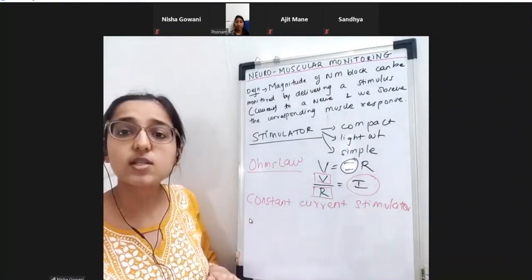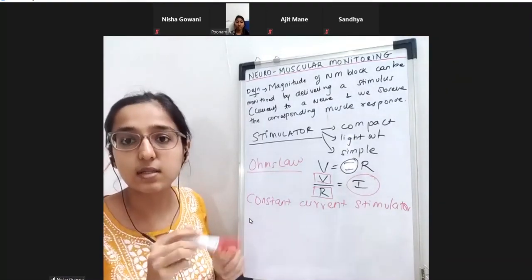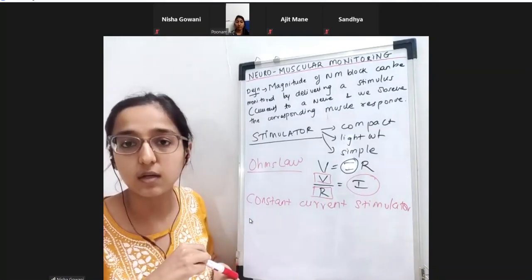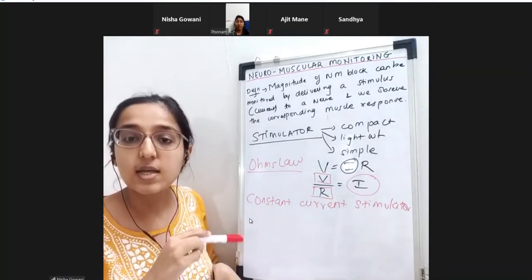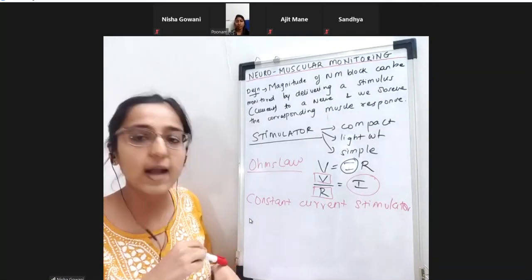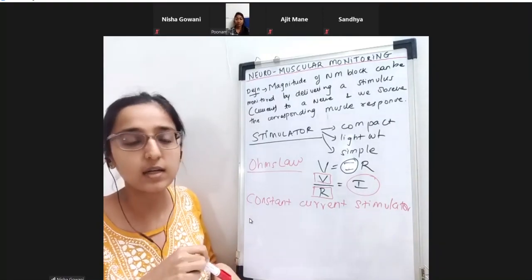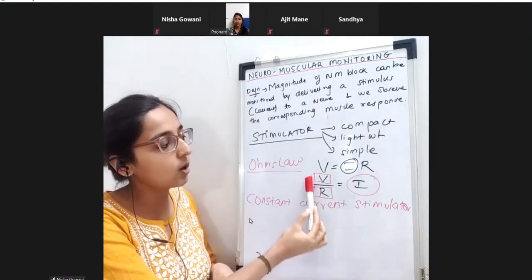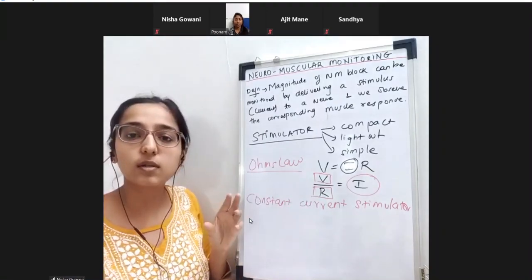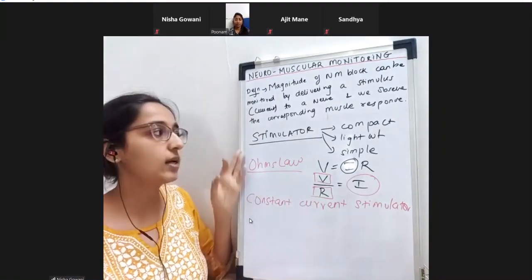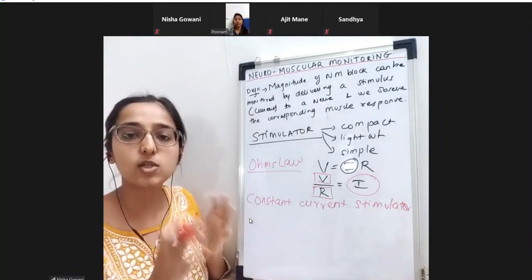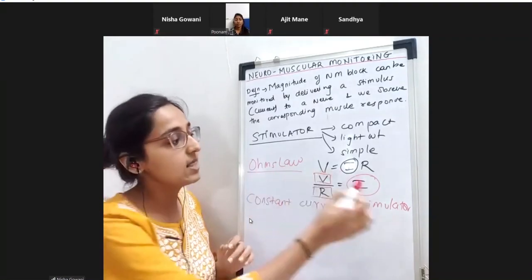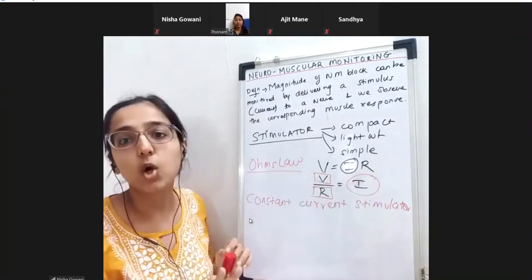Resistance is going to be offered by the skin and whatever tissues are there. That resistance can vary, and if the resistance varies, the voltage will change accordingly - the stimulator has that property. But in the end, the output current will be constant.